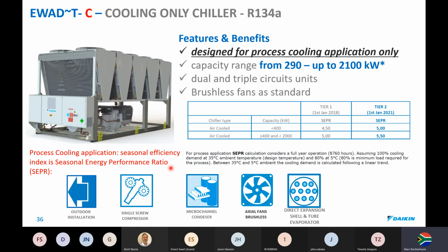Its energy performance is calculated differently, and we calculate on average a full year of operation of 8,760 hours, and we're going to assume 100% cooling demand. So this thing's virtually going to run at 100%, and it takes into calculation if you run down to 80%. So if this is a process cooling application, this is the chiller to use. It comes with a C for the process cooling application.